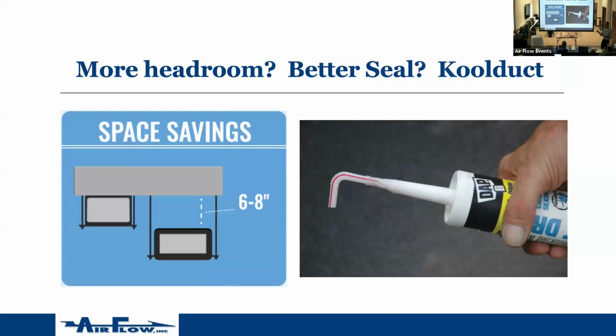Just a fun fact, when you build Koolduct, because it's duct and insulation, you can run it all the way up to the deck. Whereas if you have low pressure duct, any ductwork, you have to leave 6 to 8 inches above it so you can get 2 layers of insulation over the top. So if you've got a tight ceiling space, and all the architects want their ceilings as high as they can, this is a way to give them something that they want.